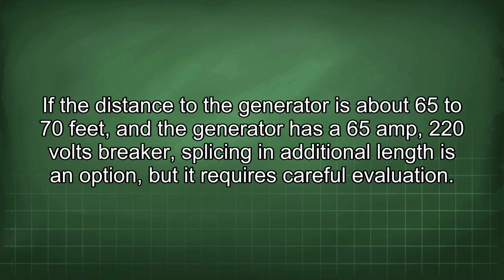If the distance to the generator is about 65 to 70 feet, and the generator has a 65 amp 220 volts breaker, splicing in additional length is an option, but it requires careful evaluation.